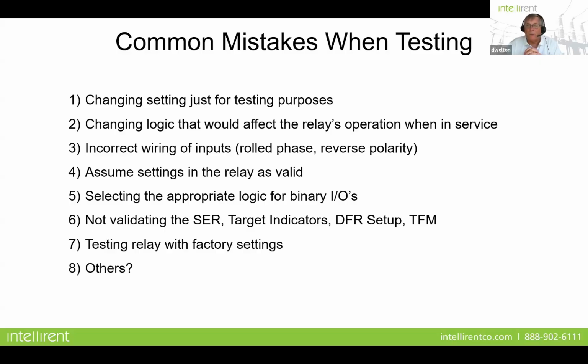Don't change the logic that will affect the relay's operation when in service. Okay, keep the logic as it will be in service. Keep all your settings and all your logic as it's going to be installed when you're doing your testing. Incorrect wiring of inputs, rolled phase, reverse polarity. I get calls all the time, people doing their distance element. Hey, it's going in the wrong direction. I said, you got a rolled phase. Don't assume that the settings in the relay are valid, either the set points or the logic.